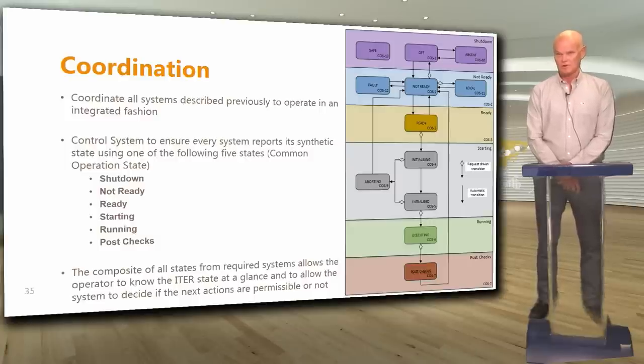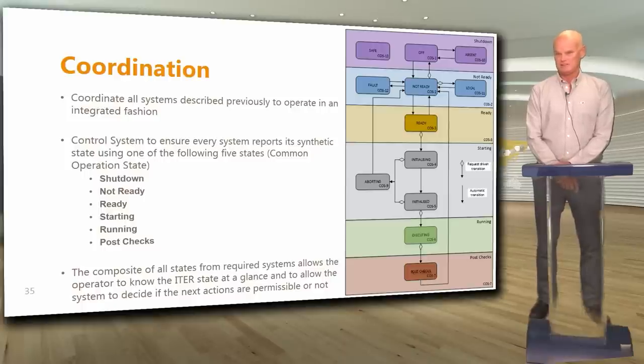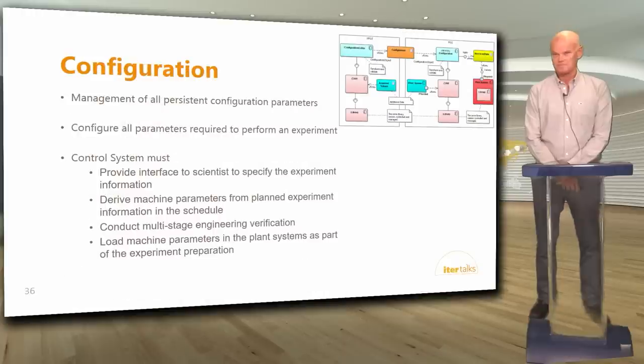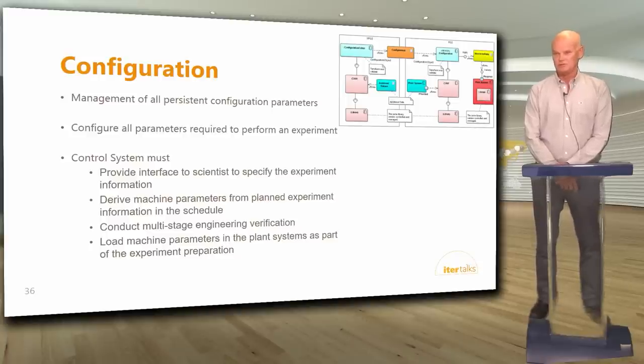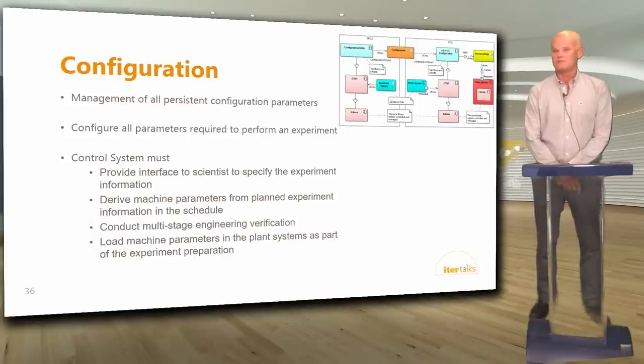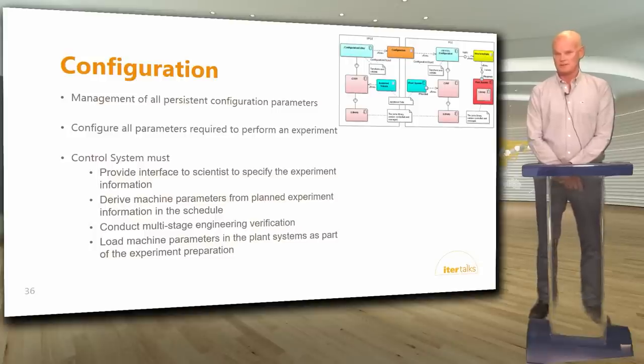Then we need coordination. All systems need to be operated in an integrated fashion. We have defined synthetic states which all systems must obey, and the composite of all states allows the operator to know the ITER state at a glance and to permit or prohibit the next action. We also have a lot of configuration to manage — all these persistent configuration parameters must survive system reboots, reinstallation of both hardware and software. We also need to manage all parameters required to perform an experiment; the control system must provide an interface to the scientist to specify the experiment, derive machine parameters, conduct engineering verification, and load those parameters into the plant system.